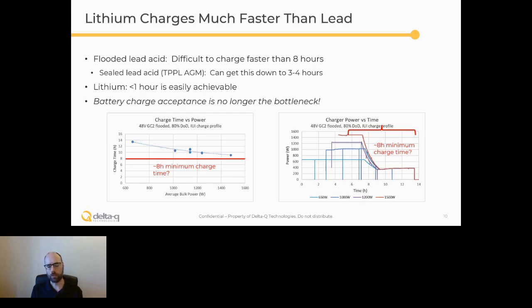I've charged here with a range of powers from 650 watts to 1500 watts. And then I've actually lined these up not with the same starting time, but with the same ending time. So what that shows there on the right is that as the bulk time decreases, as you have higher power, so you spend less time in the full power bulk, you still tend to spend just as much time in constant voltage absorption, and in particular in that low constant current finish phase. That just takes a certain amount of time.